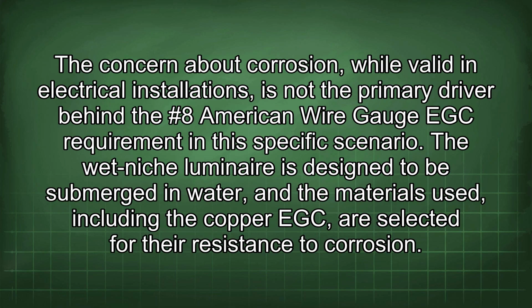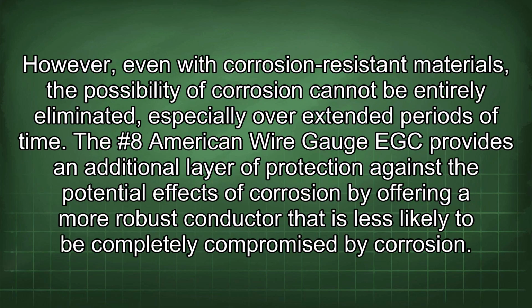The concern about corrosion, while valid in electrical installations, is not the primary driver behind the #8 American wire gauge EGC requirement in this specific scenario. The wet niche luminaire is designed to be submerged in water, and the materials used, including the copper EGC, are selected for their resistance to corrosion. However, even with corrosion-resistant materials, the possibility of corrosion cannot be entirely eliminated, especially over extended periods of time. The #8 EGC provides an additional layer of protection against the potential effects of corrosion by offering a more robust conductor that is less likely to be completely compromised by corrosion.